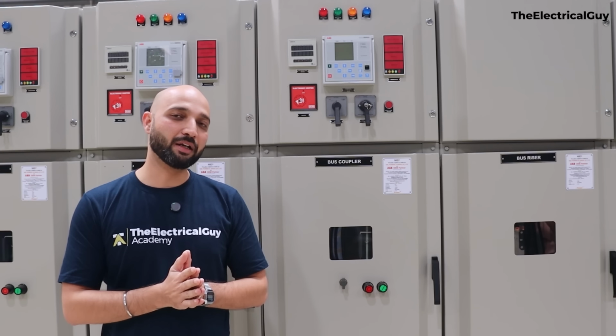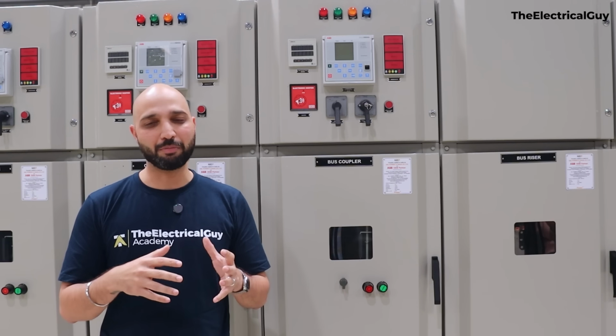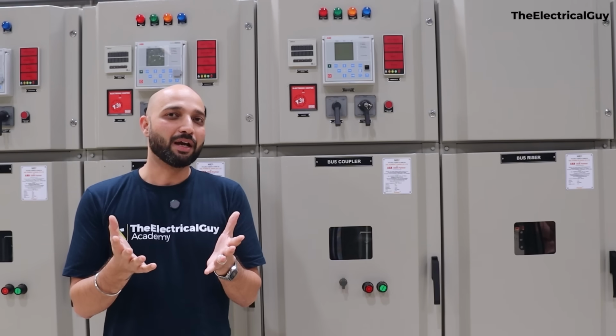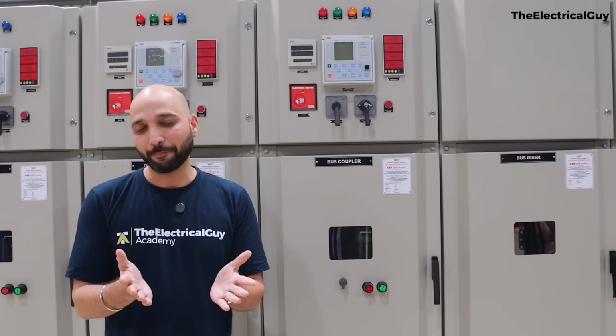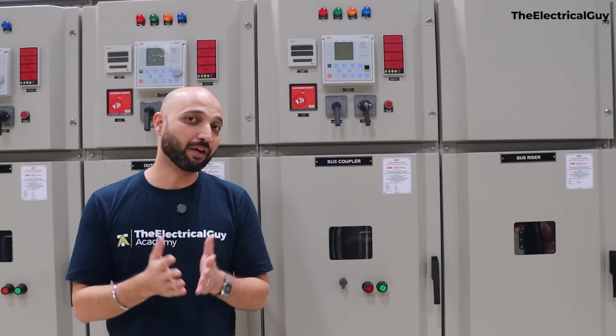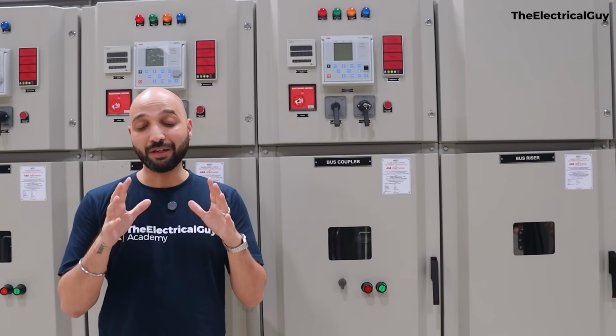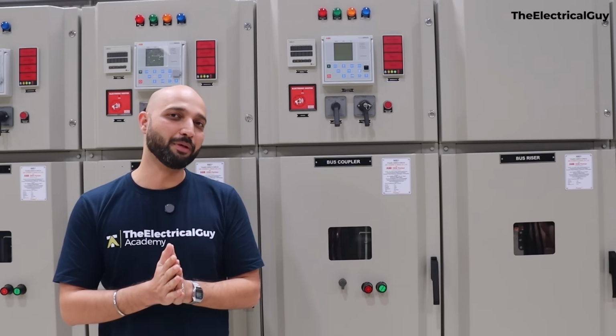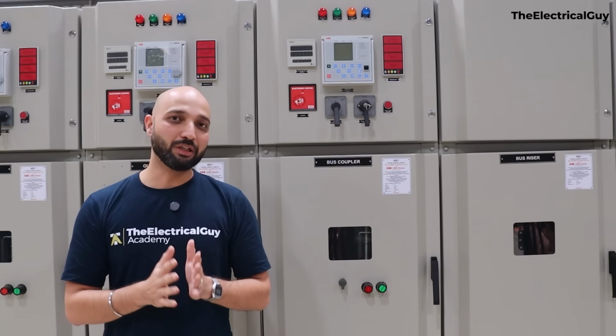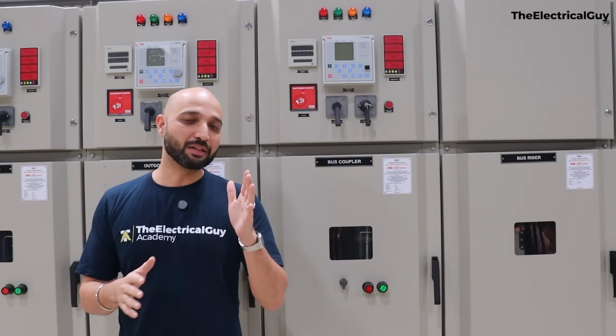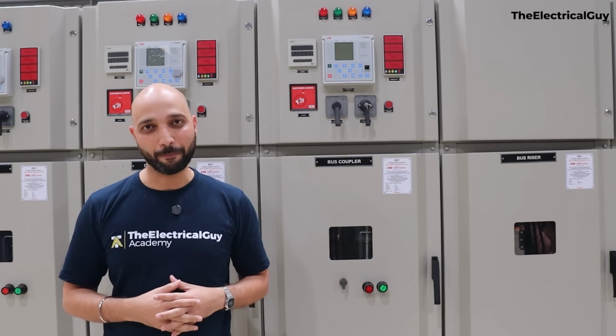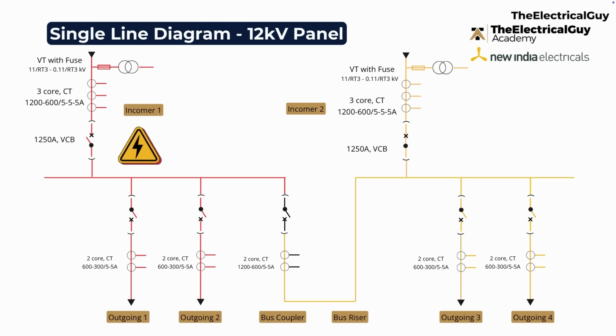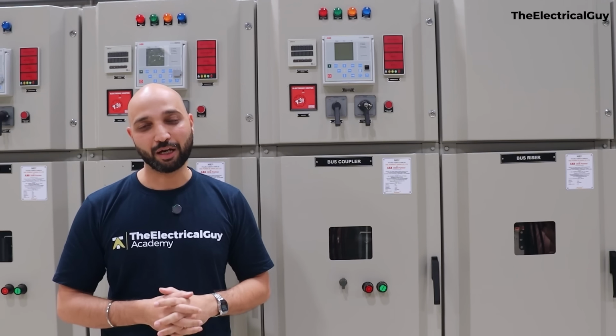And imagine if we have connected a very critical customer, for example, maybe a data center or a hospital, and they lose the supply, it's a big thing, right? If it is connected in a factory, the factory will lose millions and millions. So we need supply redundancy, supply reliability. So we need a backup plan. So even in case Incomer 1 fails, we can still feed our customers, feed our load. And since we already have incoming 2 coming from a different location, we can actually connect these two supplies together. We can couple these two supplies together so that we can get the reliability of supply that we want.